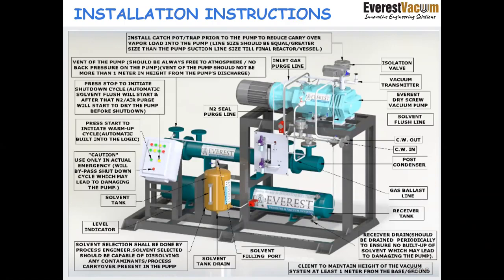In many cases we have seen that the clients have been operating the systems via the emergency button. They have been stopping the system using this emergency button, which is highly not recommended. The reason being, there are certain modules pre-fit into the PLC like start cycle and shutdown cycle. So if it is directly shut down, that stop cycle won't operate and the pump won't be cleaned. So there is a caution that this emergency switch has to be used only in case of actual emergency. Otherwise, it may seriously lead to damage of the pump.